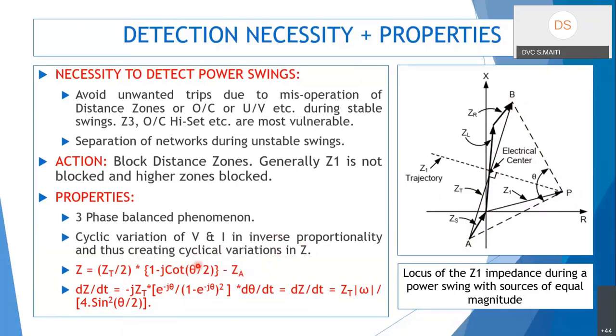This equation has the condition that EA equals EB — the voltages at both terminals are assumed equal and the line is lossless. If you differentiate this equation, the rate of change of impedance comes to approximately ZT × ω, where ω = dθ/dt, the rate of change of the angle. The change of impedance is related to the change of this angle.